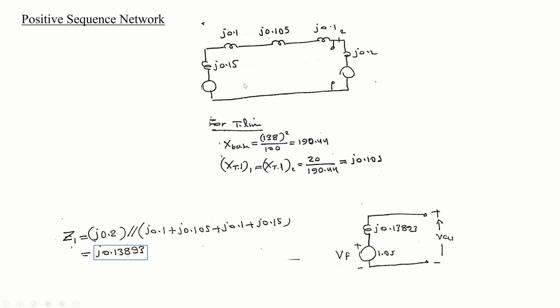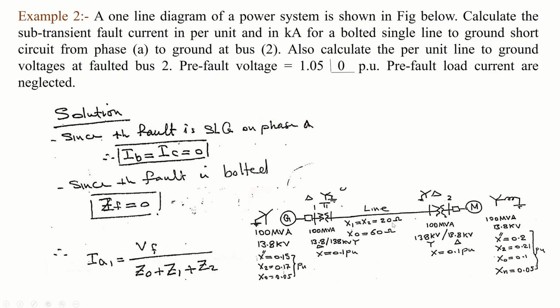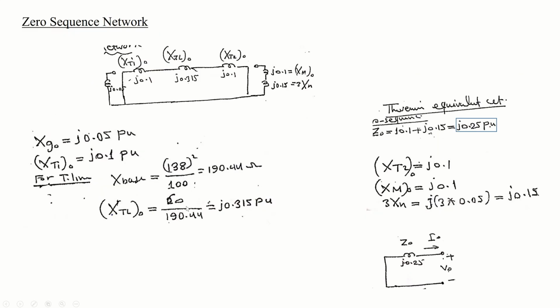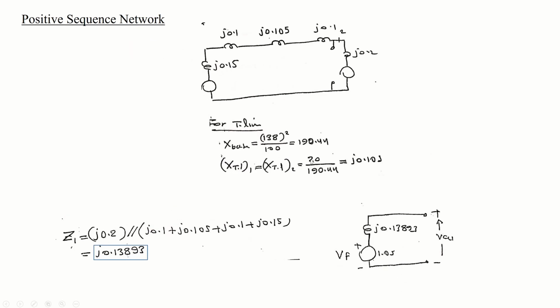So Z1, as I mentioned, the positive sequence has a source, so you need to put the source. The voltage for this, the Vfault given, is 1.05, and Z1 is this value, and Va1 is this. Okay. For the transmission line, you have this base, because you're going to take it for positive and negative. So the value of the positive and negative, if you see in the circuit, this is the positive and negative, and this is for the zero. So when I calculate, this is what we took for the zero, and this is for the negative and positive 20. So you're going to divide the actual over the base, and you'll get this value.